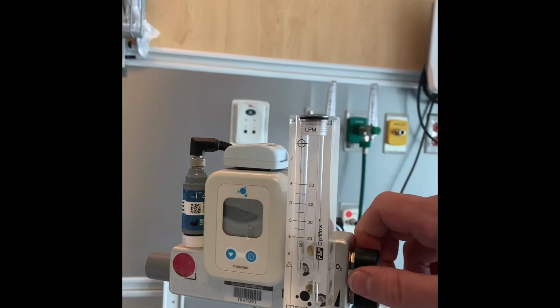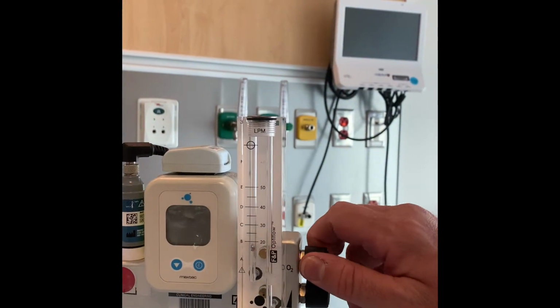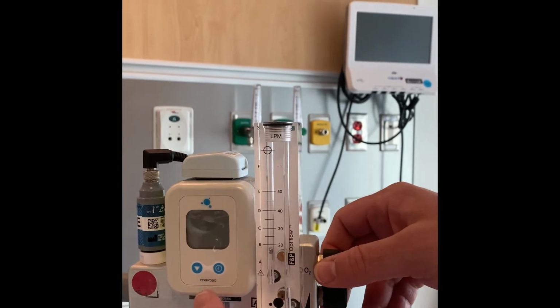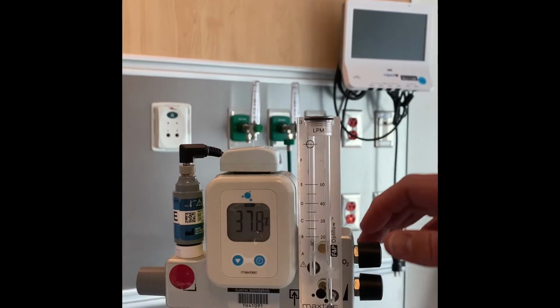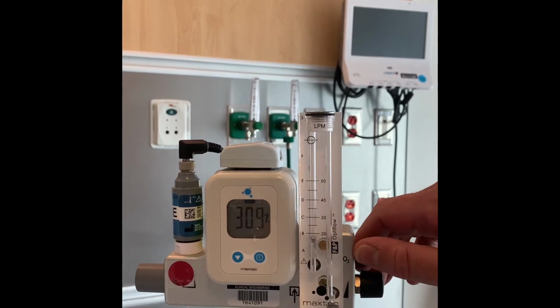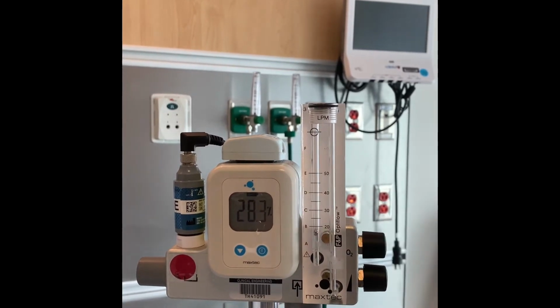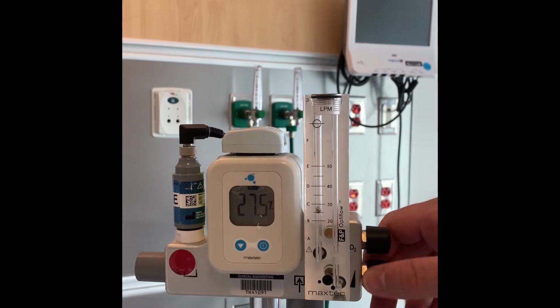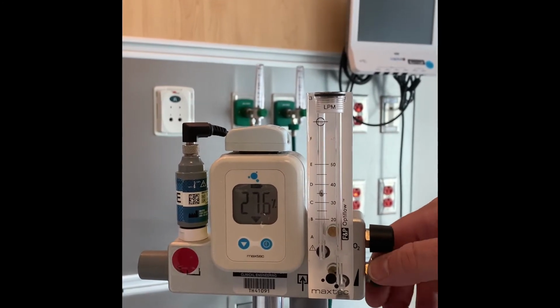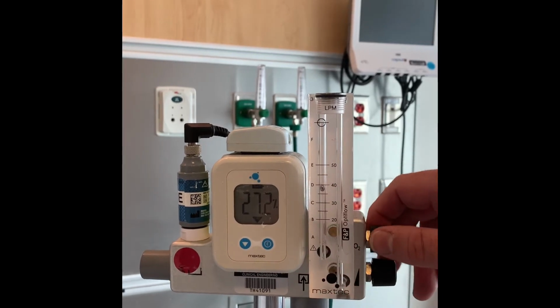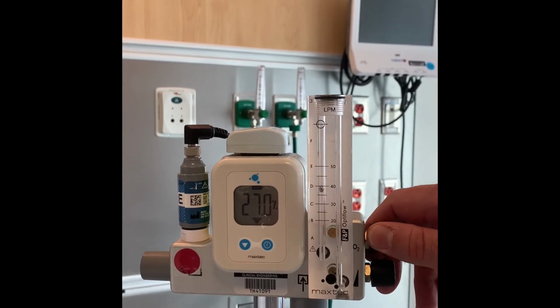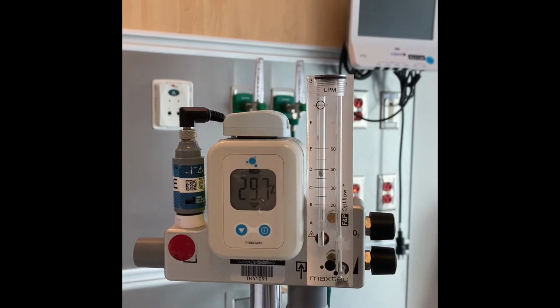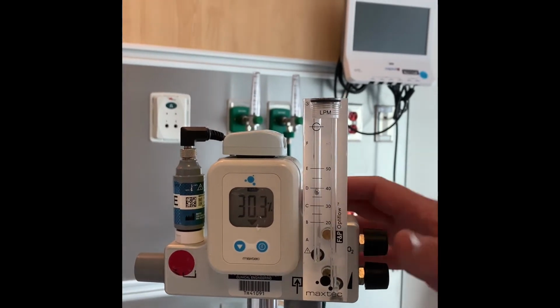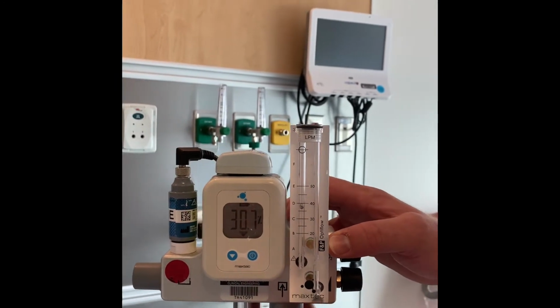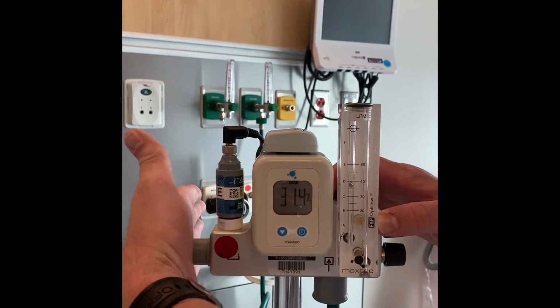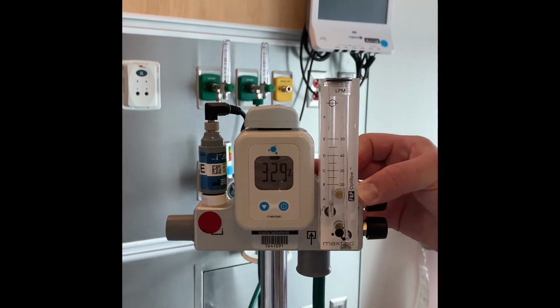Now, the knob above says O2. This is where you entrain your oxygen. So, clockwise turns the oxygen down, and counterclockwise turns the oxygen up. So right now, we have somebody set at 40 liters, and let's say roughly 30%. And it's all sucking in air and then blowing it out over here. So that's how the device works.